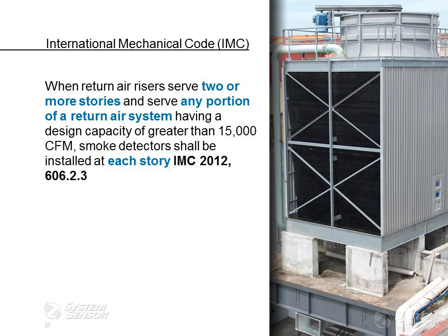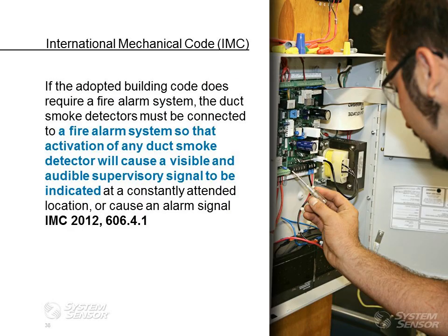When return air risers serve 2 or more stories and serve any portion of a return air system having a design capacity of greater than 15,000 CFM, smoke detectors shall be installed at each story. Also, if the adopted building code does require a fire alarm system, the duct smoke detectors must be connected to a fire alarm system so that the activation of any duct smoke detector will cause a visible and audible supervisory signal to be indicated at a constantly attended location or cause an alarm signal. Basically, what it's saying is if you're in a building and it has duct detectors and it has a fire alarm system, they have to be connected together.